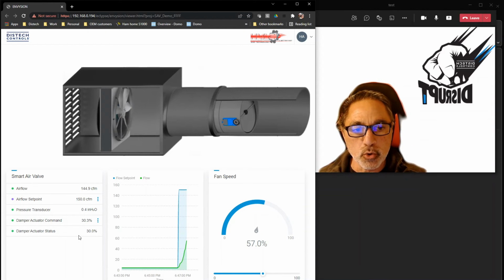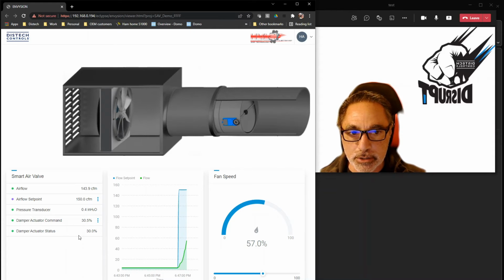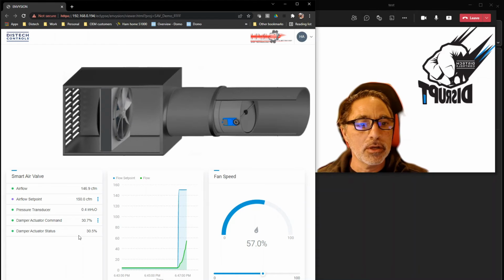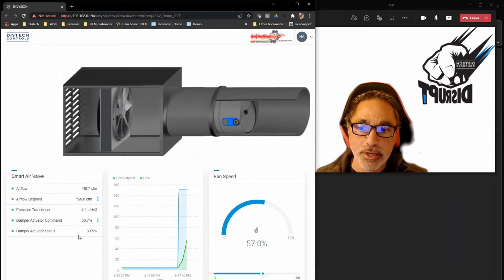The reason this is very accurate is that our controller has a communicating bus that goes to the actuator and the transducer, and it's continuously communicating back and forth. So it's not a discrete input, which many VAV boxes out there are. What I mean by that is it's not a hardwired input. A transducer is not a hardwired input, and an actuator is not a hardwired input like an analog output. This is truly a communicating device to the two input devices it needs to control this valve. And the algorithm that's running is where all the math happens. It is measuring accurately and opening the damper to the right position at the right time to make sure it's not going to overshoot or undershoot. And as you can see right now, I'm about 148.7 CFM, very close to my set point.